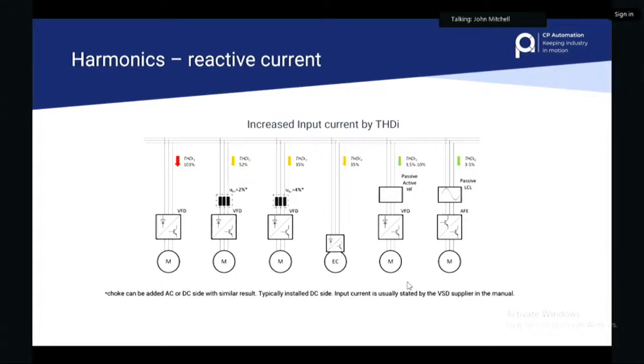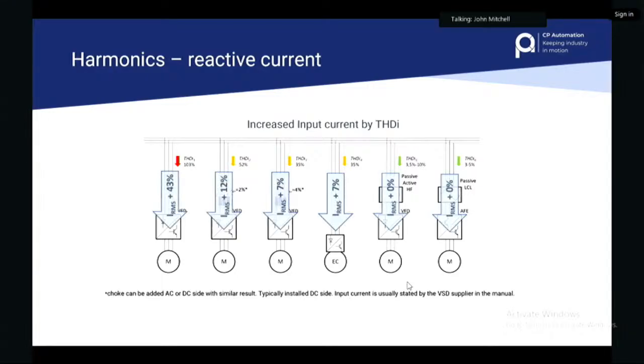And you can see on the right-hand side, the green ones are obviously the better ones because they're going to be less than 5%. If you keep THDI below 5%, the THDV from the transformer will also be below 5%. In addition to that, you have extra losses because the THDI is a distortion which creates losses. So if you don't get rid of the distortion, you're wasting current and energy.